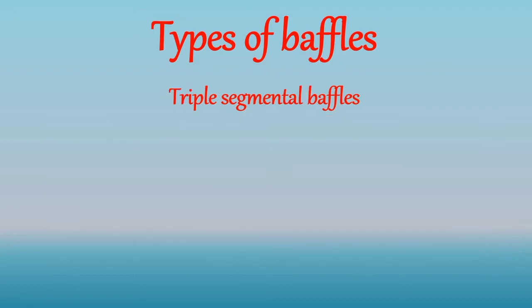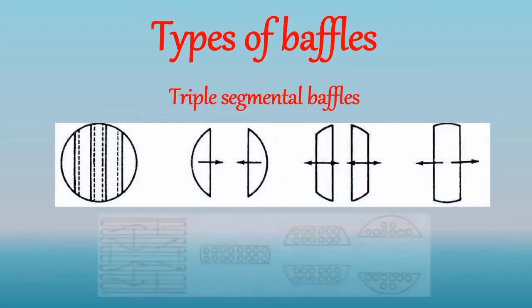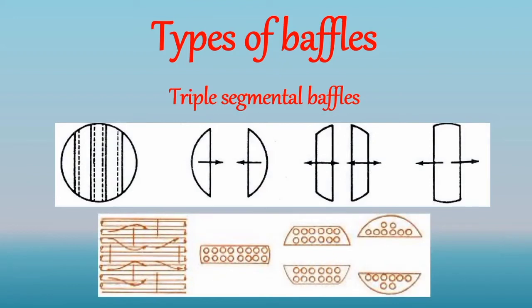In the triple segmental baffle, the baffle plate is cut in such a way that we get three parts: one center baffle and two split baffles. In triple segmental baffles, all the tubes are supported by all the baffles, which provides low pressure drops and minimum tube vibration.